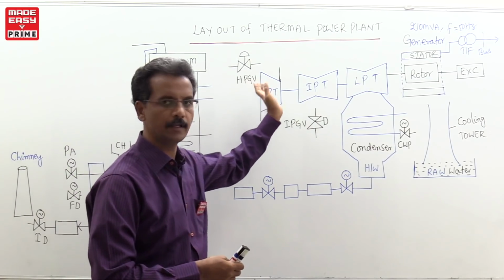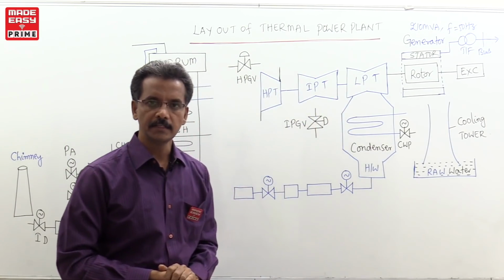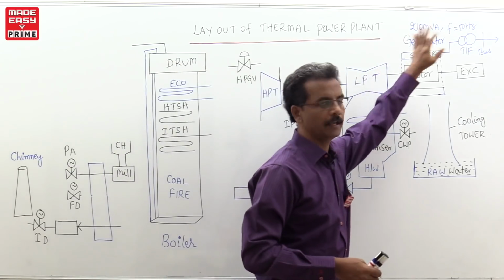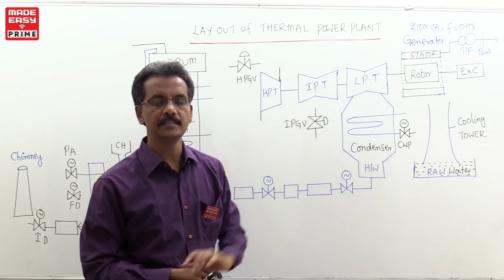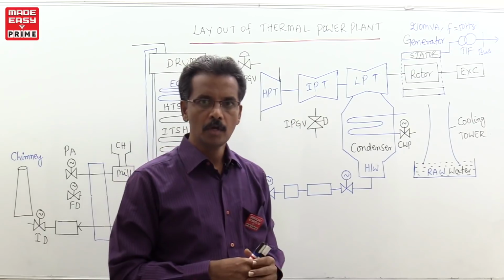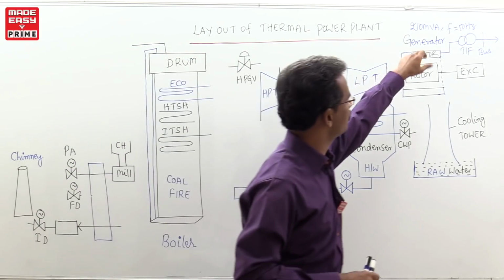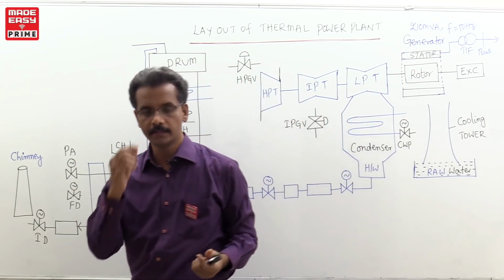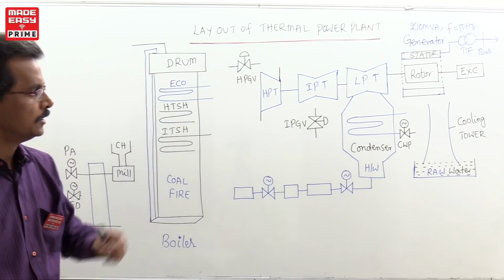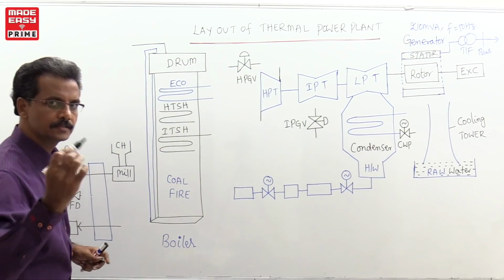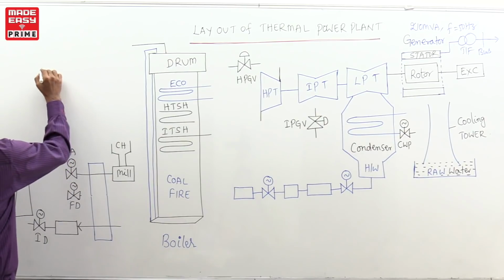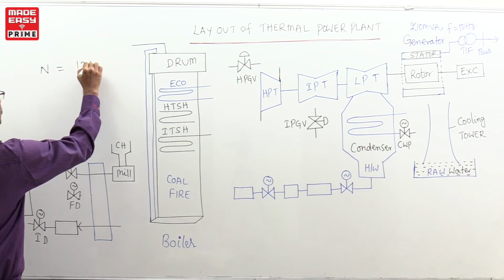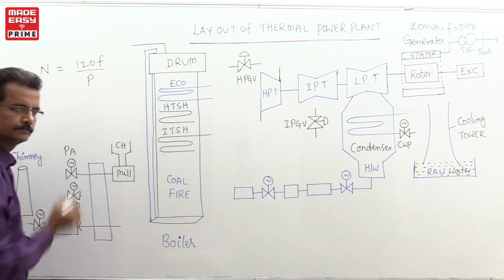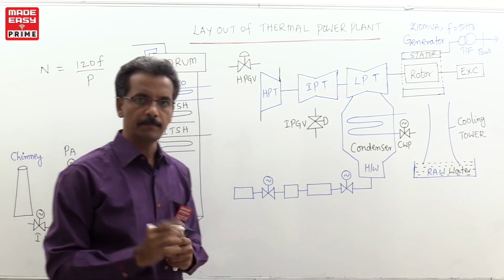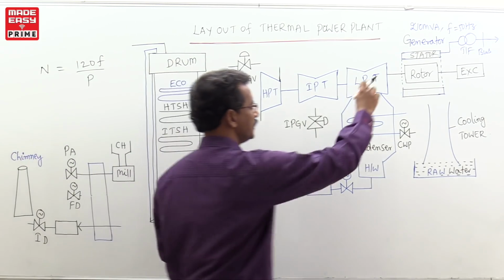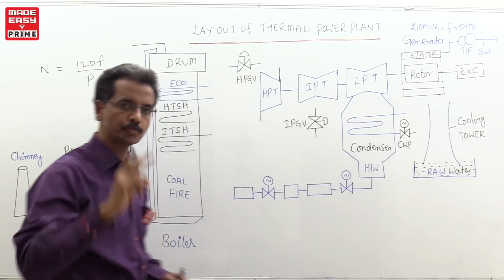The heat energy is converting into mechanical energy inside the turbine, and mechanical energy is converting into electrical energy inside the generator. So now, for producing this 50 hertz frequency of the generator signal, you can think of a simple logic here. What is the speed of the generator? This is given by 120 F by P, where F is the frequency and P is the number of poles. In a practical generator, the number of poles is 2.